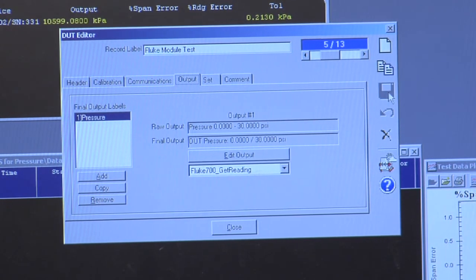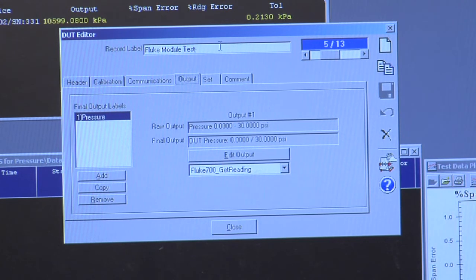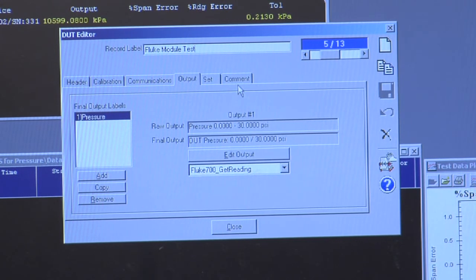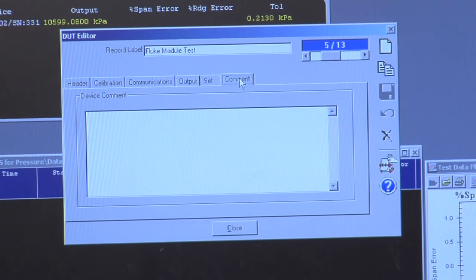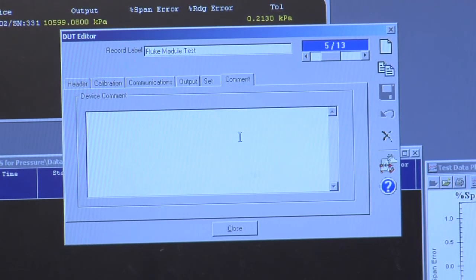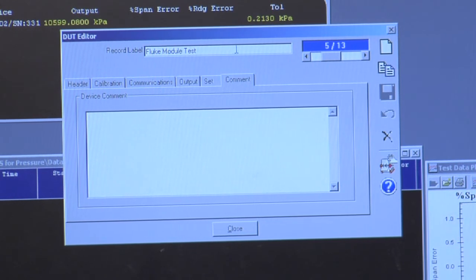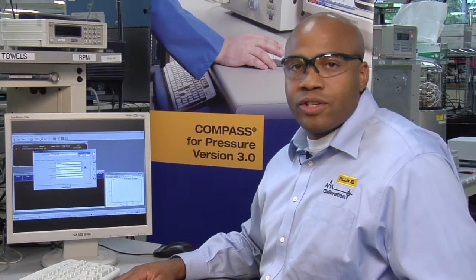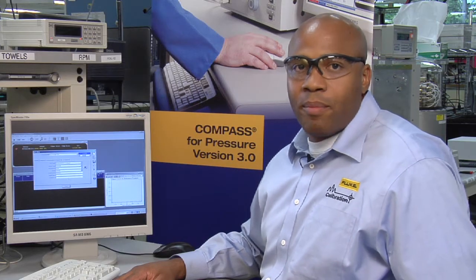So if I save it, it's saved as Fluke module test. If I wanted to, I can also add a comment that would give me specific information for the future. So I've just completely set up the pressure module.